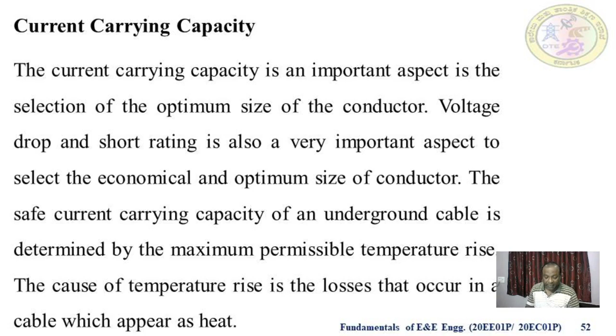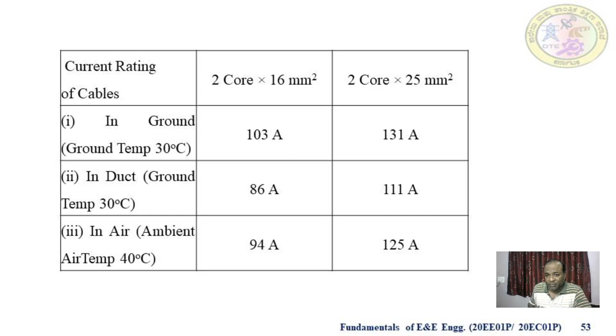Here some current ratings are given for the cables. Underground, at a ground temperature of 30° Celsius, a 2 core by 16 mm square cable is rated 103 amperes, and 2 core by 25 mm square is 131 amperes. In duct, at a ground temperature of 30° Celsius, 2 core by 16 mm square has 86 amperes, and 2 core by 25 mm square has 111 amperes. In air, at an ambient air temperature of 40° Celsius, a 2 core 16 mm square cable has 94 amperes, and a 2 core 25 mm square cable has 125 amperes.